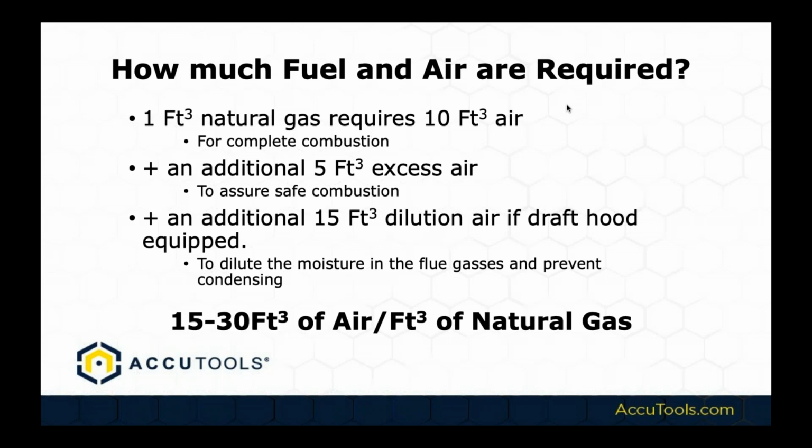Typically when we talk about how much air is required, for 1 cubic foot of natural gas, it requires 10 cubic feet of air for complete combustion, and an additional 5 cubic feet of excess air for safe combustion. So we always mix in a little bit more air than we need, because we want to make sure that every gas molecule contacts an air molecule so we get a complete combustion of the flue gases.